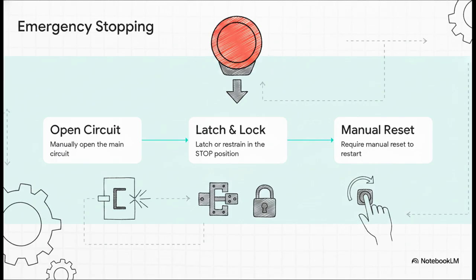First, the device has to manually open the circuit. Second, and this is absolutely vital, it must literally latch or be physically restrained in the stop position. It locks into place. And third, it demands a manual reset before anything can be restarted. This way, if you slam the emergency stop on, say a massive industrial saw, the thing doesn't just unexpectedly jump back to life the second you let go of the button. You have to consciously, manually reset the system once the danger is actually gone.